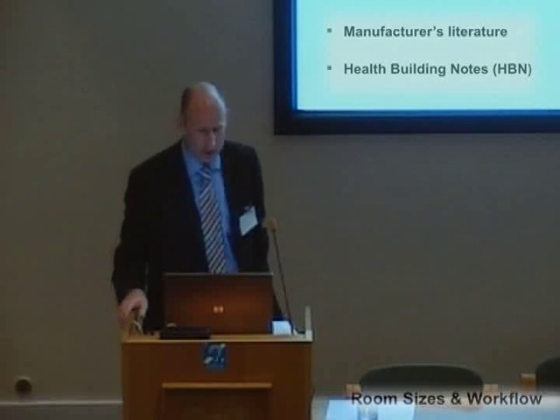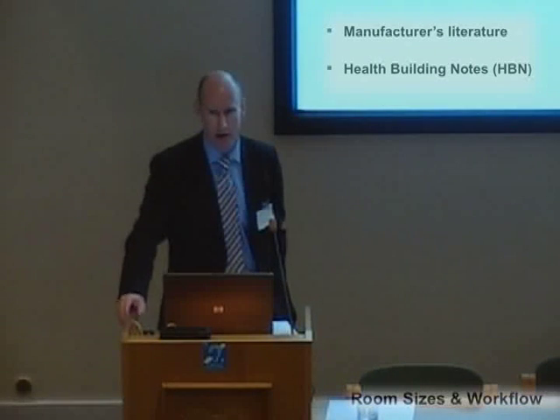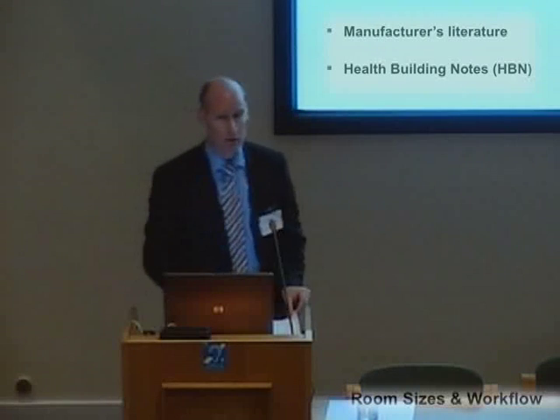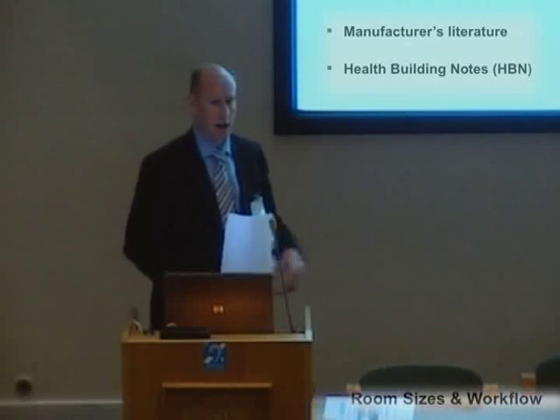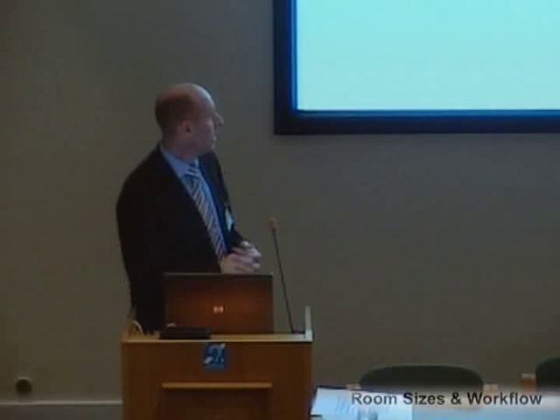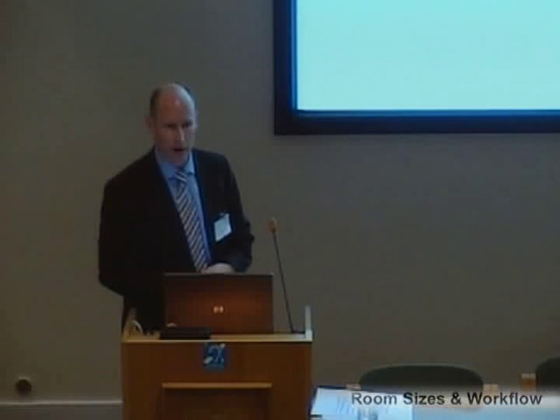Basically, you will find in the manufacturer's literature minimum requirements. Occasionally, you will see a recommended room size, but minimum requirements, which again is fine, but not necessarily from a workflow perspective. Also, in the HBNs, you will see those minimum requirements slightly larger, but I wouldn't necessarily use them strictly. As we heard earlier, they're a little bit out of date. The room size might be big enough, but you do get irregular room shapes and sizes. So my message to everybody is to get the manufacturers involved as early as possible in any project so that we can give you at least some guidance on our equipment, if not necessarily on workflow. We've got expertise in our organisation which can help with workflow, but mainly on the equipment size, at least we can give you some guidance on the size and shape of rooms.